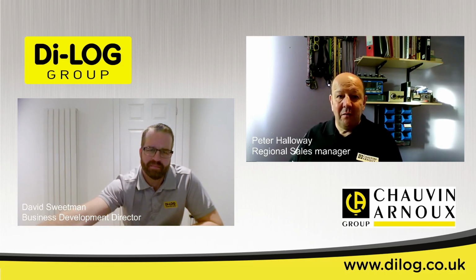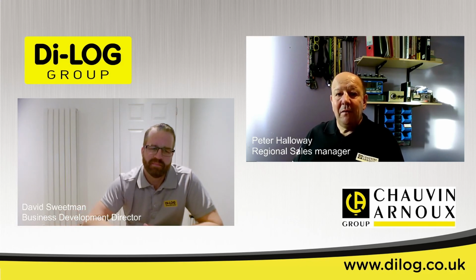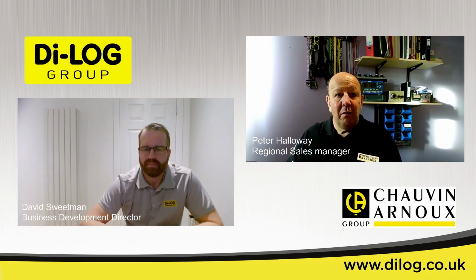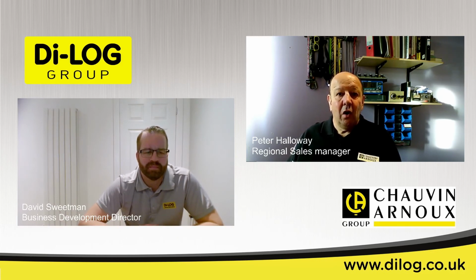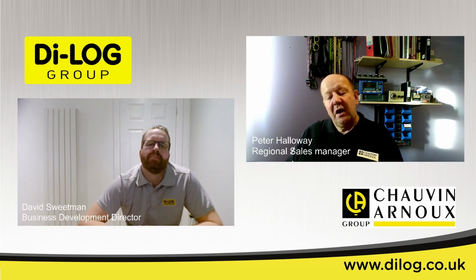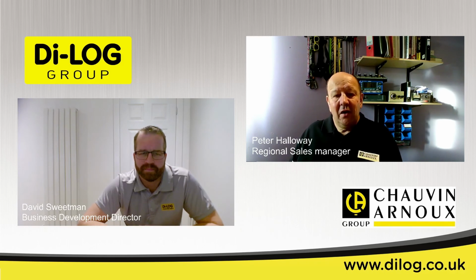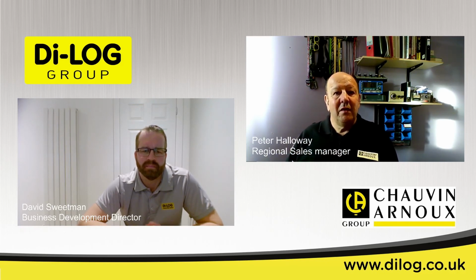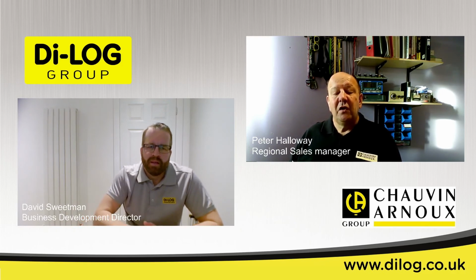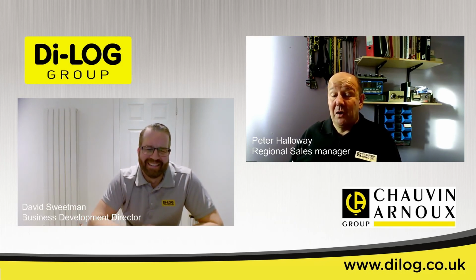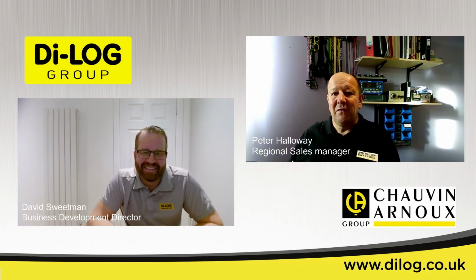So harmonic orders, we talk about the third, the fifth. If we talk about the fundamental, most of us know in the UK the fundamental frequency of our supply is 50 hertz. That's known as the fundamental. The second harmonic is 100 hertz, the third is 150 hertz. You can see the pattern, going up and up, in 50 hertz increments. In the US it will be in 60 hertz increments. That's what the harmonic orders are, with the fundamental being 50 hertz.